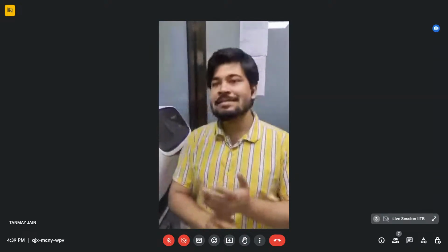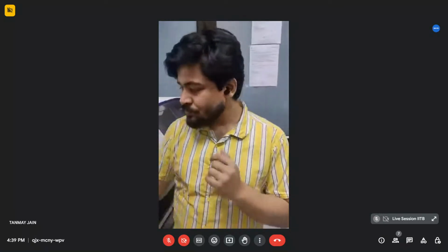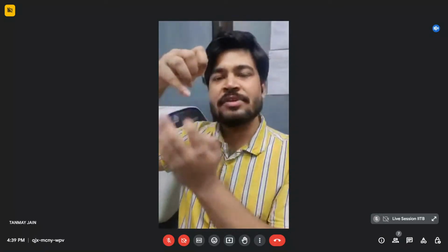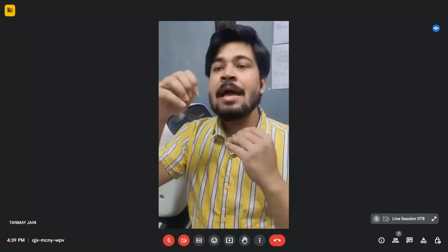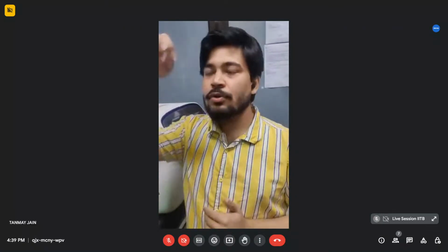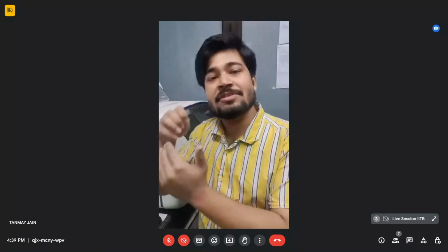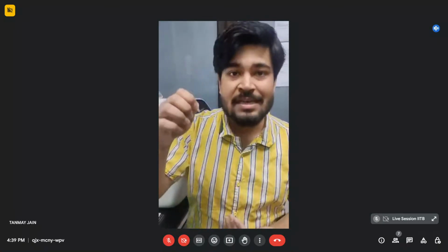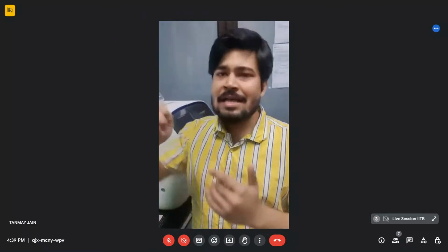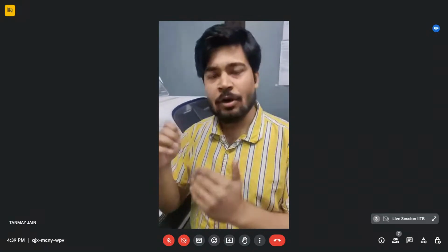As you can see here, white light is incident from this region onto each of the sensors that get attached to it. The instrument analyzes the interference of the white light that gets reflected back from two surfaces. One is the surface of the sensor itself, and the second is from each molecule that gets bound, one layer after the other. Based on the sensor chemistry, we can use streptavidin sensors, and then we can take a biotin ligand, and similarly many other chemistries are available.